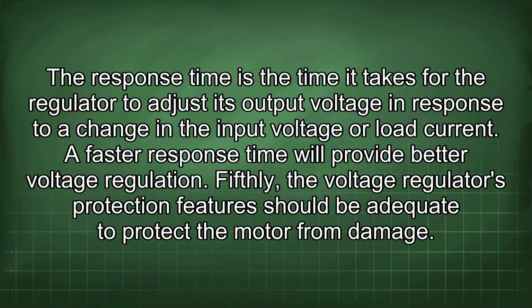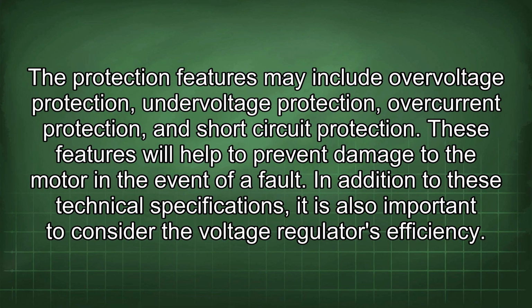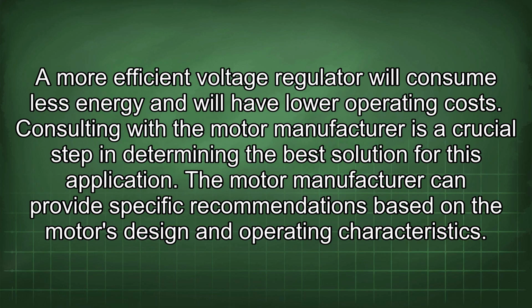Fifthly, the voltage regulator's protection features should be adequate to protect the motor from damage. The protection features may include overvoltage protection, undervoltage protection, overcurrent protection, and short-circuit protection. These features will help to prevent damage to the motor in the event of a fault. In addition to these technical specifications, it is also important to consider the voltage regulator's efficiency. A more efficient voltage regulator will consume less energy and will have lower operating costs.